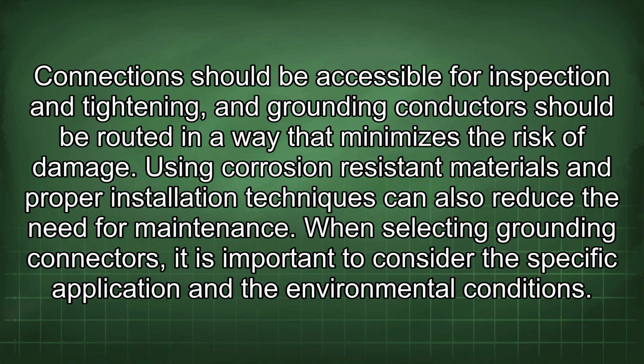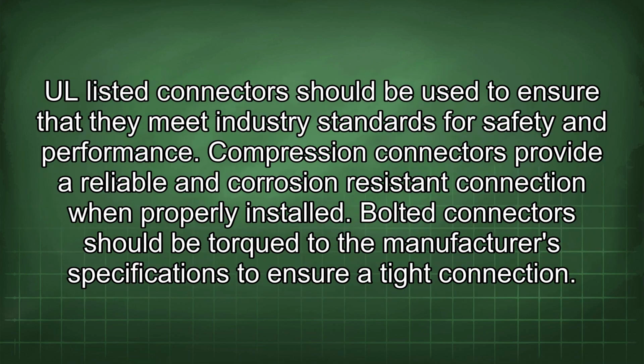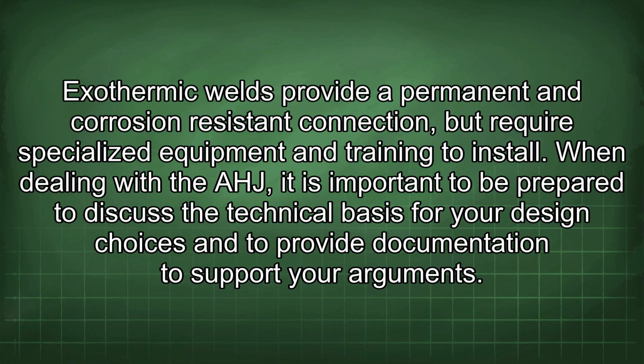When selecting grounding connectors, it is important to consider the specific application and the environmental conditions. UL-listed connectors should be used to ensure that they meet industry standards for safety and performance. Compression connectors provide a reliable and corrosion-resistant connection when properly installed. Bolted connectors should be torqued to the manufacturer's specifications to ensure a tight connection. Exothermic welds provide a permanent and corrosion-resistant connection, but require specialized equipment and training to install.